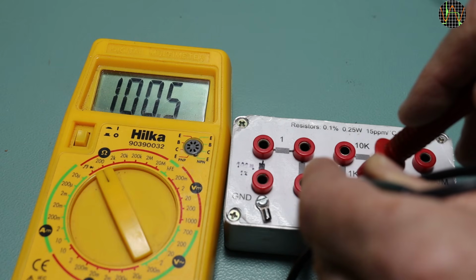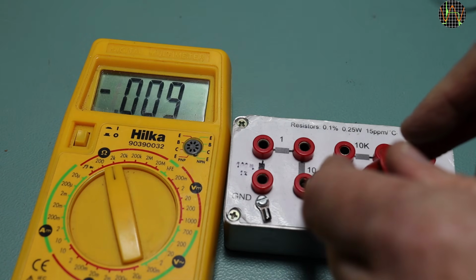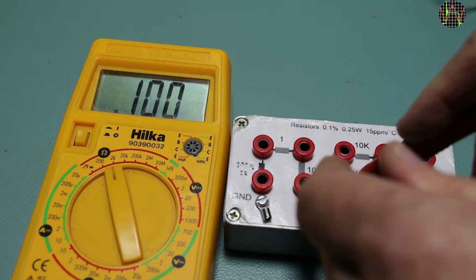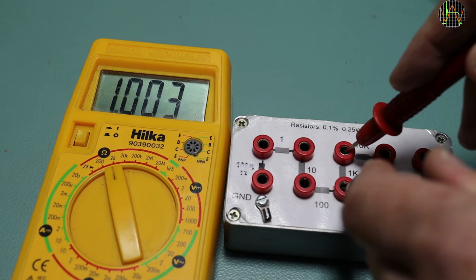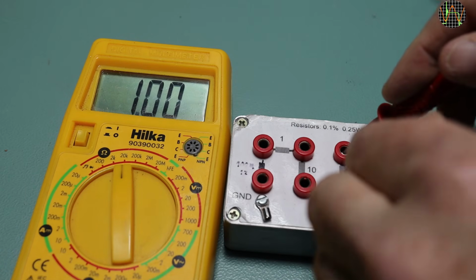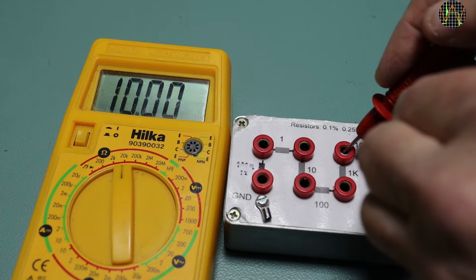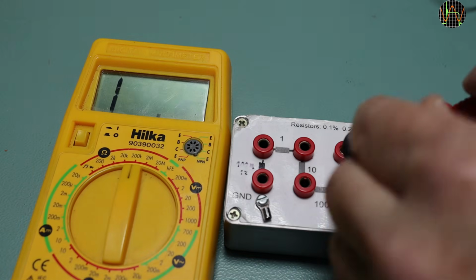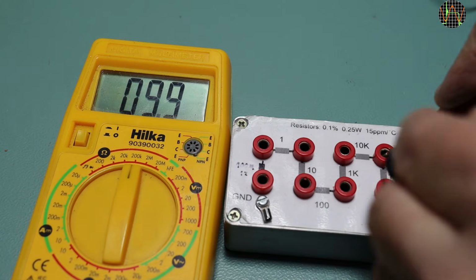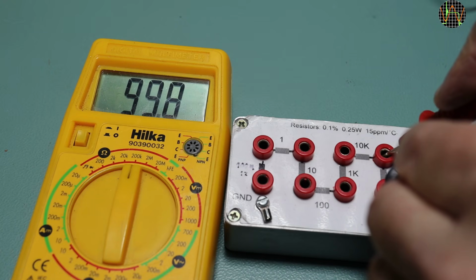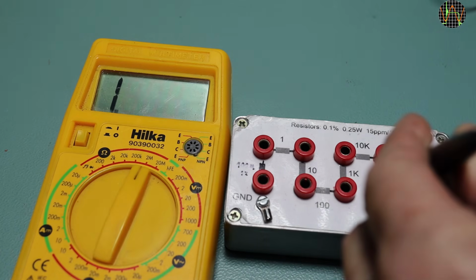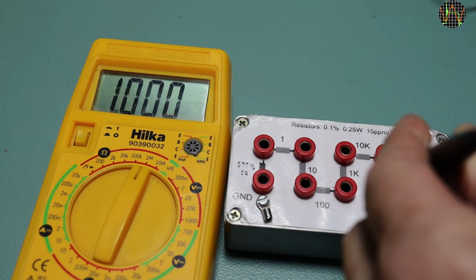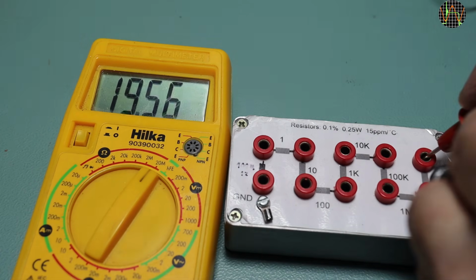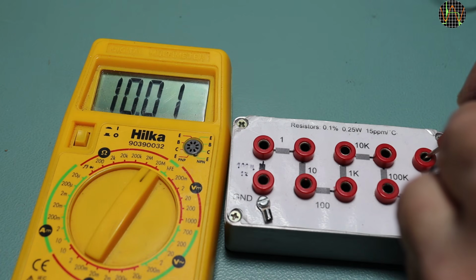100 ohms, okay. Switching to the 2K range, 100 ohms again. 1K, 0.3% high. Switching to the 20K range, 1K again, spot on. 10K, spot on as well. Switching to the 200K range, 10K again. 100K and the Hilka reads 0.3% low. Switching to the 2 meg range, 1 meg, spot on. And finally the 20 meg range, 10 meg, and it takes quite a long time, but finally it settles very close. Resistance modes are fine too.